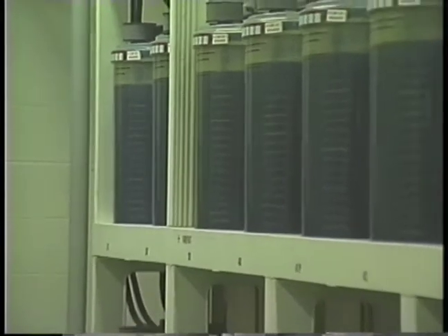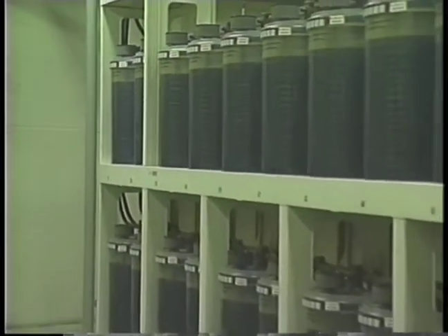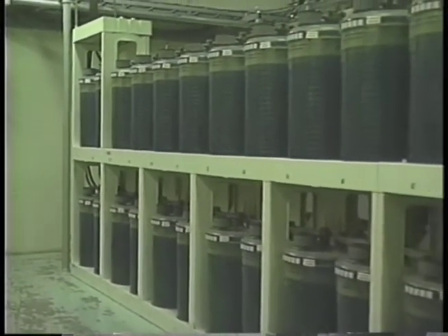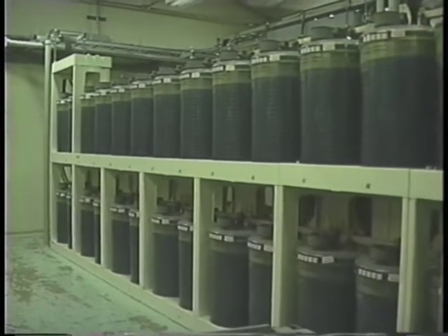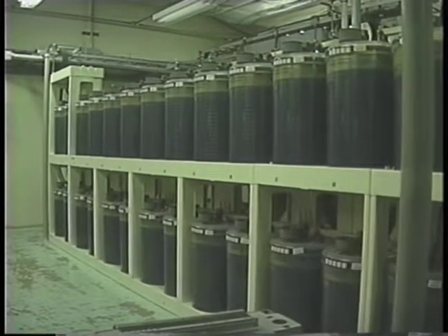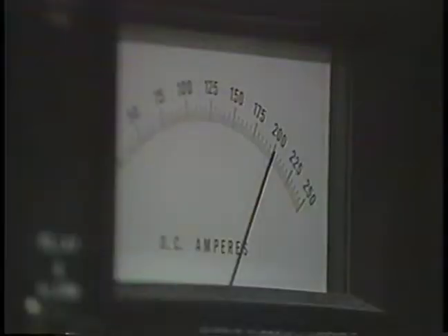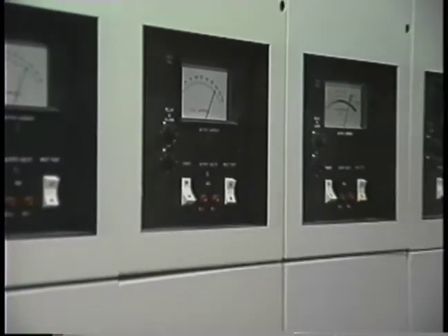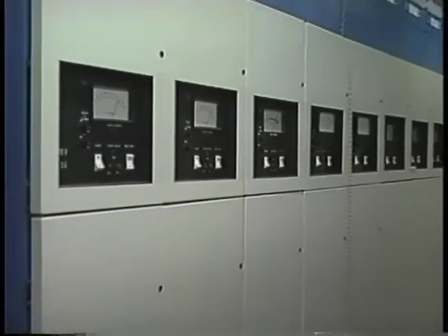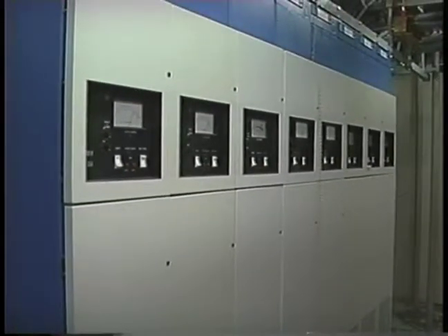These batteries power the switching system and all of the telephones when there's an electrical power failure. This string of batteries supplies 48 volts DC. Normally, the batteries are continuously charged by the charging system. The charging system powers the switching equipment and all of the telephones. This system works very much like the charging system found in an automobile.